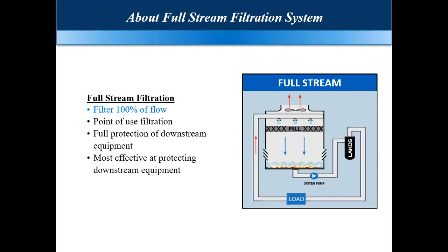So here is the basic operation of the separator, whether it is basin sweeping, side stream or full stream, right? The separator remains the same. Only the flow rate varies and the sizes of the separator vary. But the technology remains the same. It can be applied to sand filters. It can be applied to non-barrier filters. Any filter can be approached that way, right? However, the most effective filtration in a cooling tower is the non-barrier centrifugal separator, right? So I'll just go briefly through the operation of non-barrier filtration. It's an excellent design, this product.